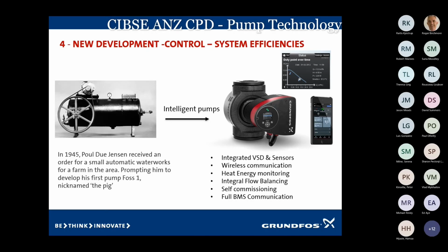That's all you got. Nowadays, there's all the bells and whistles. There's flow balancing, it's self-commissioning, it's wireless. 2 pumps or 4 pumps will talk to each other without a control panel. You've got all the sensors integrated. You can even use your mobile phone to talk to the pump for commissioning. And for the guys that are commissioning pumps these days, you can draw up the pump curve. You can dial up the pump curve on the display, and it'll show you where the pump's running, the head, the temperature, the water, the power. So much has changed to make life so much easier. More and more is going into the pump as a package. It's almost becoming its own little PLC BMS, and more accepted.